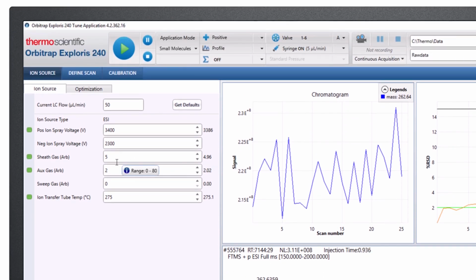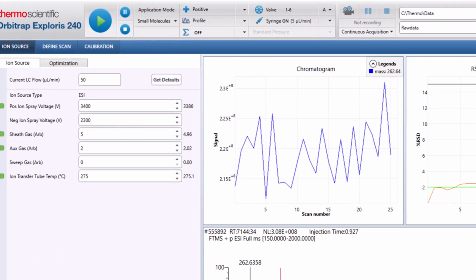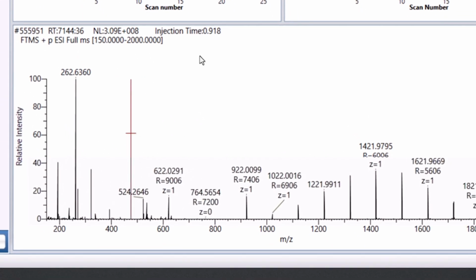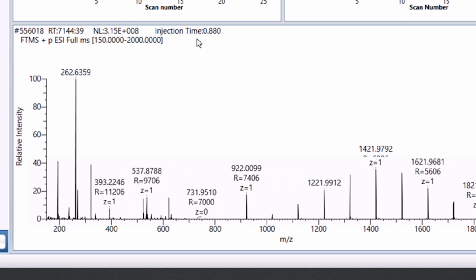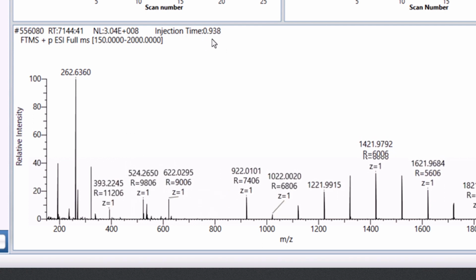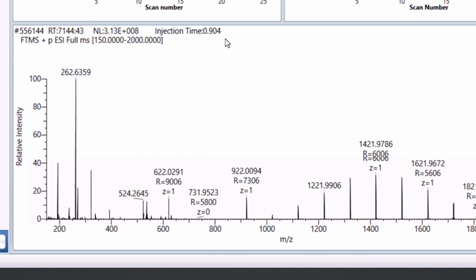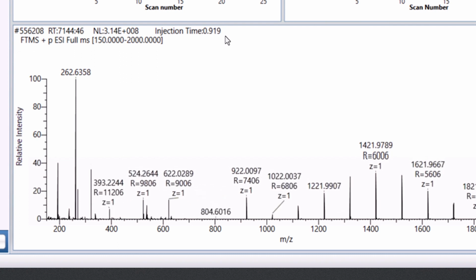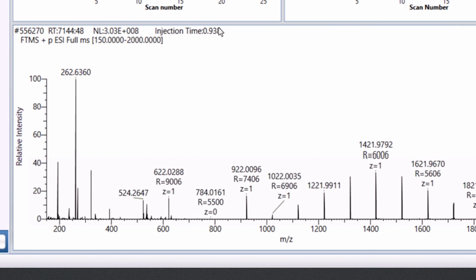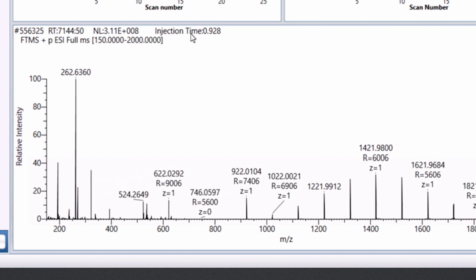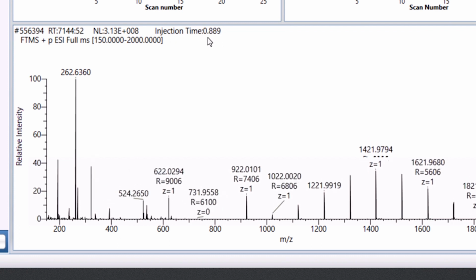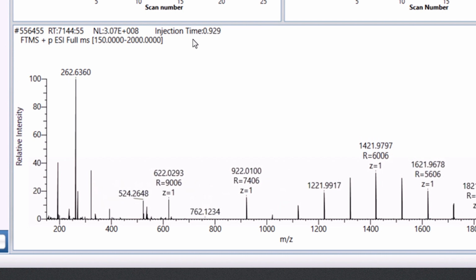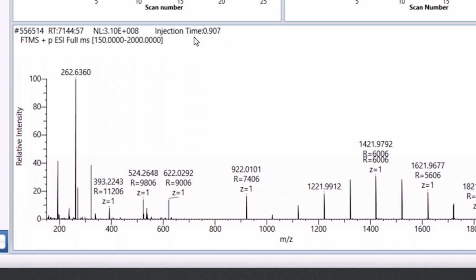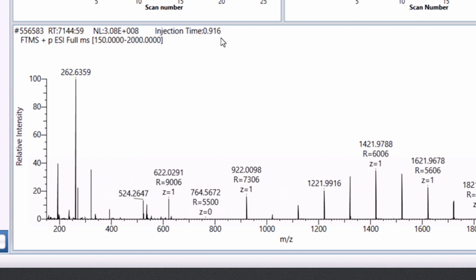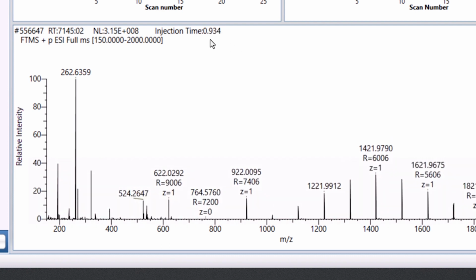So very low gas settings, and the voltages are also preset. Before I go ahead and start calibrating, I'm going to look at the injection times. You should always have below 1 millisecond. You should never get high above that. If you do, then you probably have a dirty mass spec. Maybe you need to flush some solution through the syringe needle, change your transfer tube, because that is indicative of ions having a harder time accumulating.